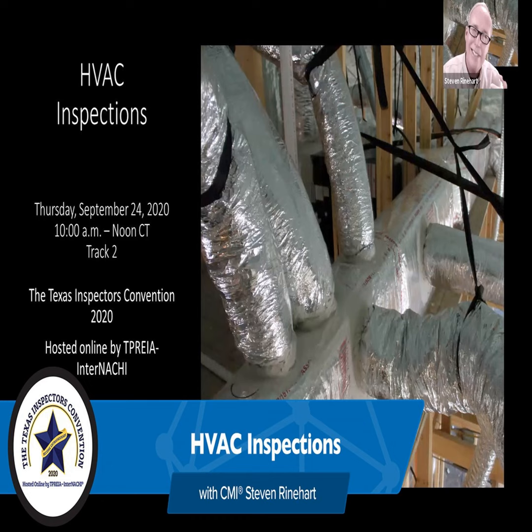So the unit usually stubs in, with a flex connector because it has a motor; it can be rigidly connected. Concealed within walls, I don't run into that. Extended through walls, floors, partitions, ceilings, I don't know if I've really seen that, but yeah, I'd look for it. I want to see it in the same room as the unit.